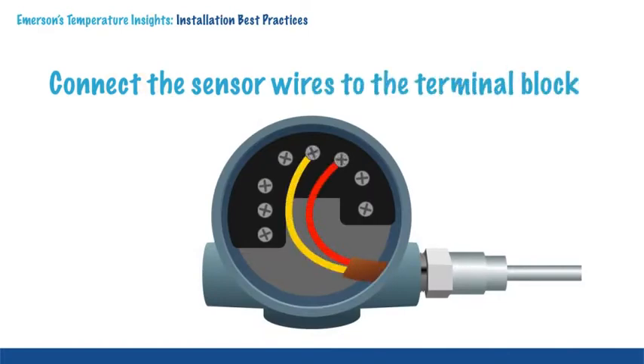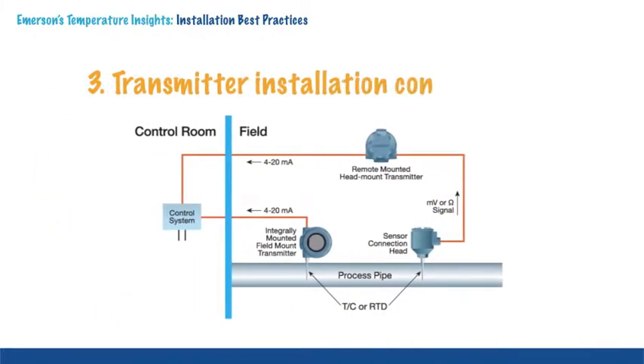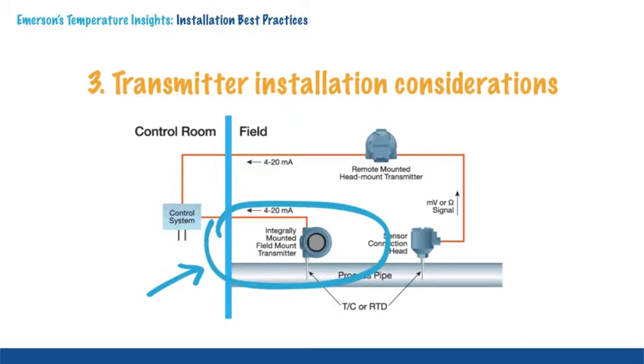After the sensor is installed, it needs to be wired to a terminal block in an enclosure or transmitter. Transmitter installation is another key consideration in the temperature installations. The preferred installation is one that is integrally mounted to the sensor and Thermowell. This is commonly referred to as direct mounting.